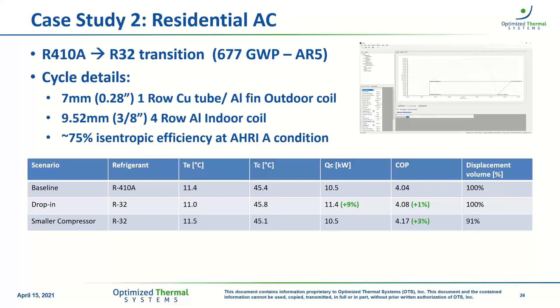This next question is also about case study two: did you keep the same system subcooling and superheat? And if not, how are those defined in this analysis? Yes, these are both using the same subcooling and superheat. There's an argument that the R32 cycle would see a lower superheat to keep discharge temperature down, and there may be some other differences. But just for the sake of the simplest cycle comparison, we're using five degrees subcooling and superheat for all cycles here, to keep everything clean.